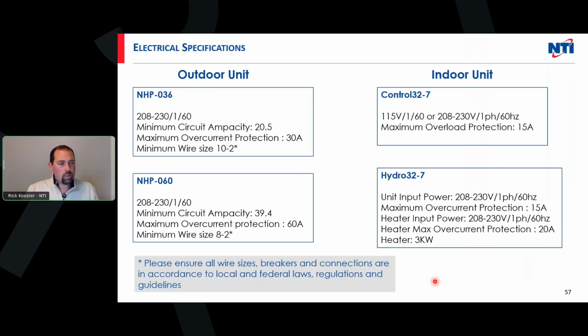All right, wiring the system, indoor and outdoor. We'll start with the outdoor unit first on the left-hand side here. So we are 208, 230 single phase, minimum circuit ampacity 20.5. So we're looking at a max circuit of 30 amps. On a 5-ton, we're looking at a 60 amp breaker. Those are just minimum wire sizes.